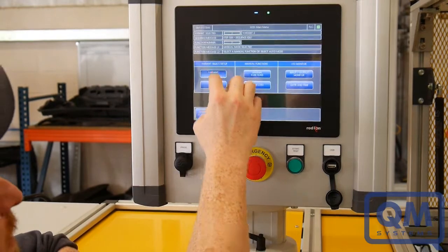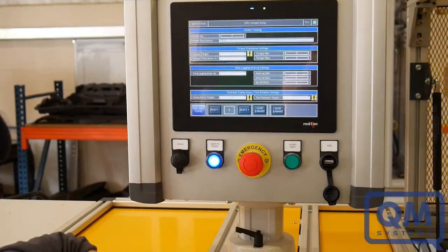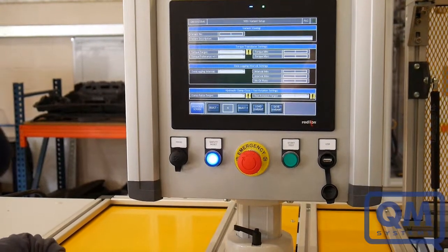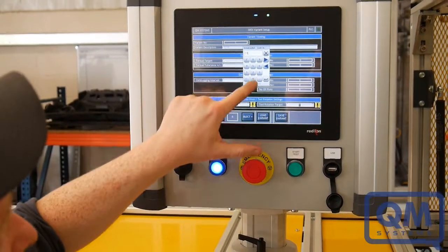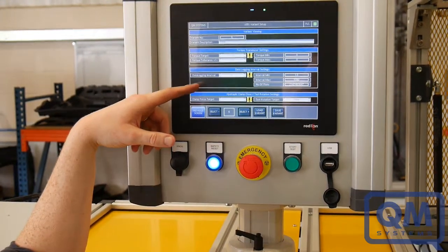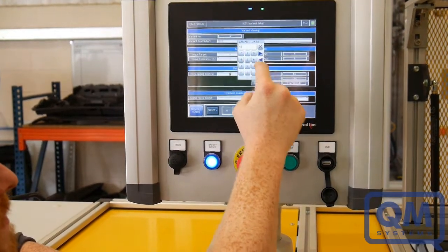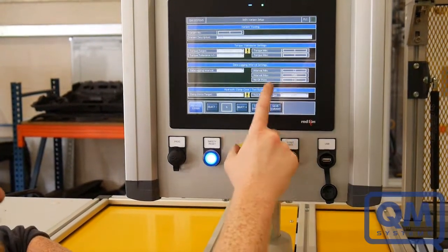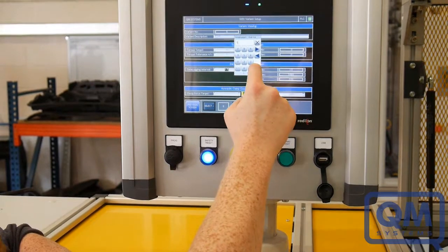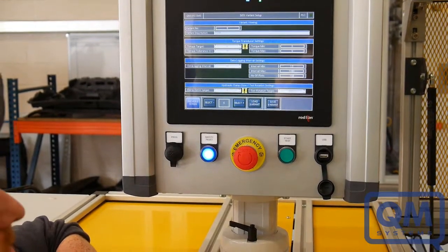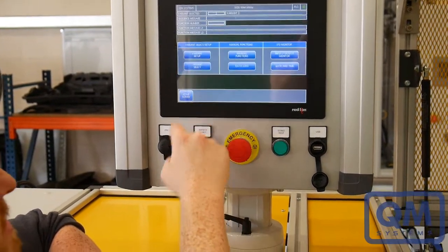The options you've got are to do the variant description, the torque target and its tolerance, the data logging interval. So with the way we're data logging at the moment, you've got a maximum of 720 plots, and whatever rotation target you put in there, it will tell you what your minimum interval is in degrees to be able to data log. So in this case, we're allowed 1.5 degrees as our lowest increment, giving you a maximum number of 720 plots to use. In this instance, you can change it to 10 degrees, so it will plot a point on the graph every 10 degrees, and that gives you 108 individual increments. Okay, so that's the variant setup.